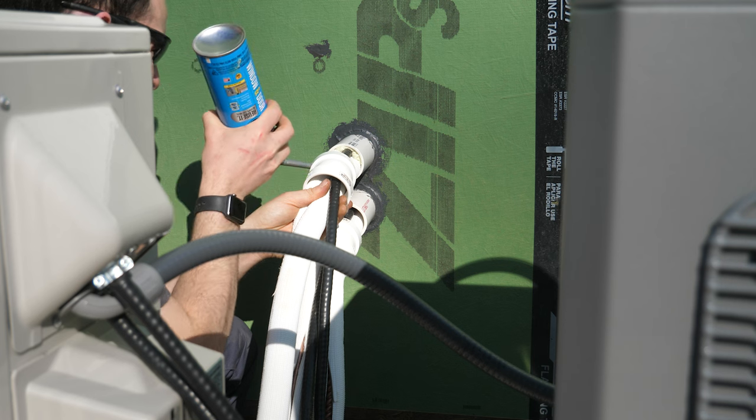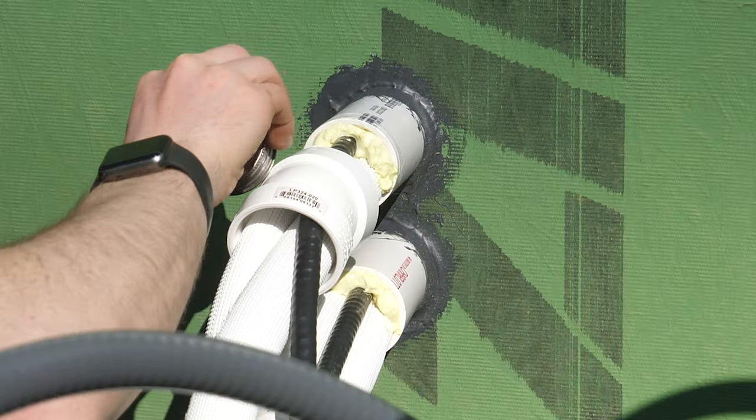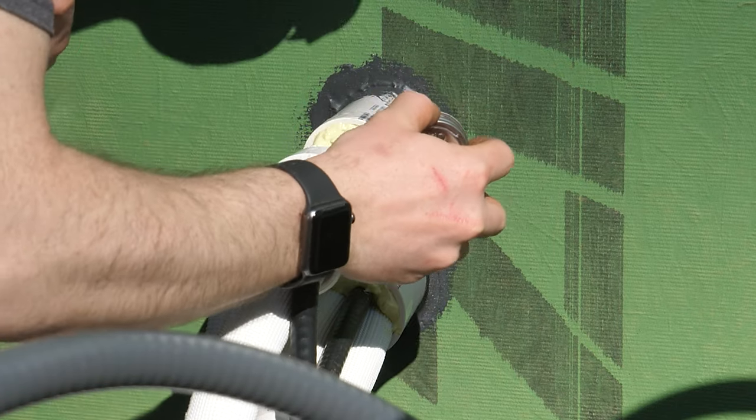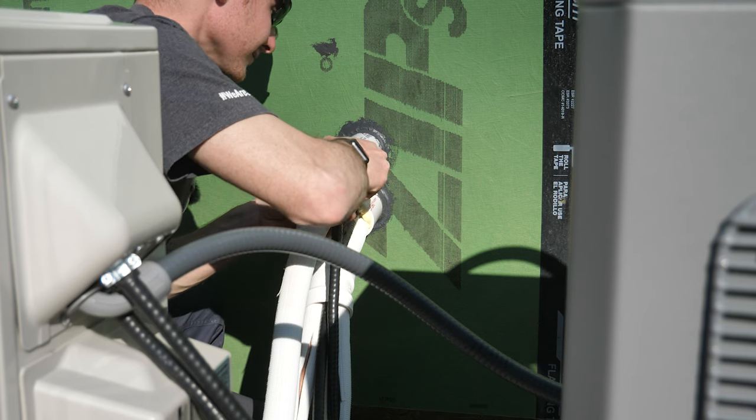Before gluing on the elbows, I used some low-expansion foam to seal around the line sets and cables. I have these pipes flashed to the wall with liquid flash for both water and air sealing, then glued on a 22.5-degree elbow to direct water away from the opening. For these AC systems you've got to have an outside disconnect as part of code, so I'm mounting mine here using one of these Diversitech mounting outlets — they're about $20.